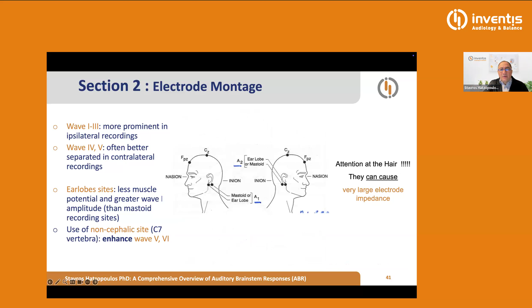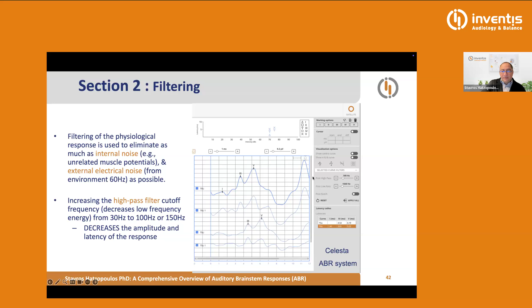What I like to speak very briefly about is the filtering. Although we do these tests in the booth, which is also shielded, a lot of times, especially if we're doing screening, which is a different ball game, we cannot do it in a shielded room. We need to use filters in order to eliminate as much as possible the internal noise of the subject and the external noise, the 50 or 60 hertz that come from all these devices that eventually we sealed. This is again from our Celesta recording, and you can see that we're using a high pass filter of 100 and a low pass filter at 1500 hertz, and we get this very, very nice response.